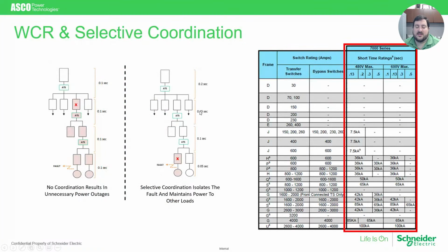To further illustrate that example and why WCR ratings are important, I'll use this graphic here. On the left-hand side, I am showing the example of a non-selectively coordinated facility. ATS is positioned at several layers in the system, but let's pretend there is a fault at the lowest layer and the circuit breakers are not selectively coordinated. If the circuit breakers are not selectively coordinated, that means that their tripping times are not necessarily in line with each other. And even though you have a fault down low in the system, a circuit breaker much further upstream may be the one to trip, the one with the X over here, because they are all non-coordinated. They all trip in about the same amount of time.